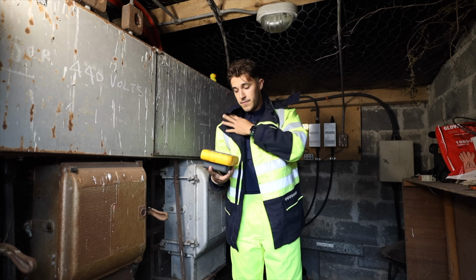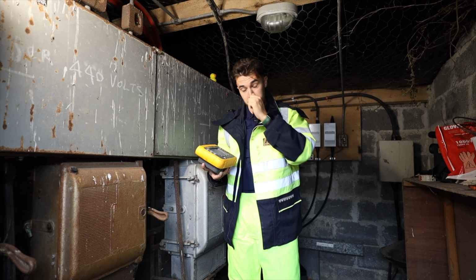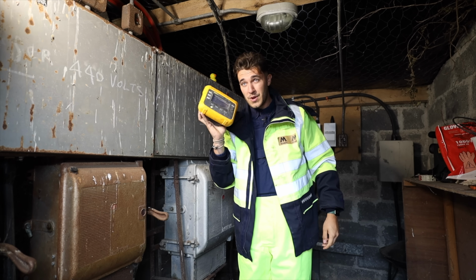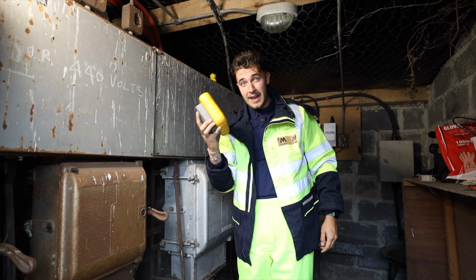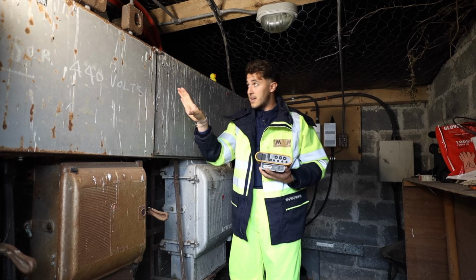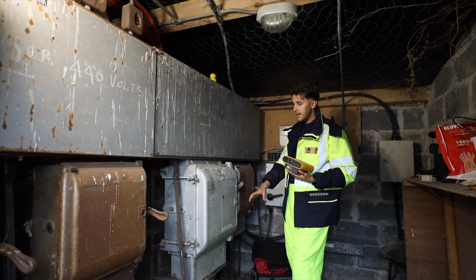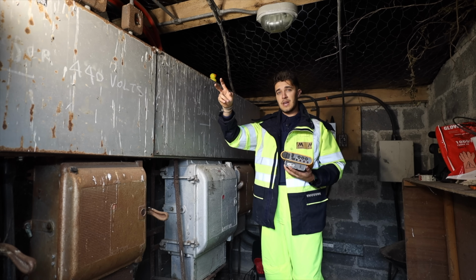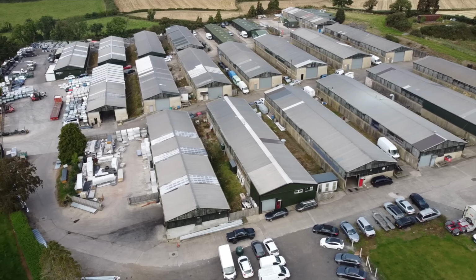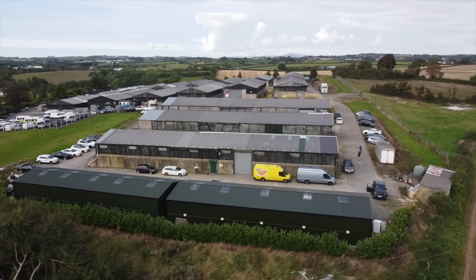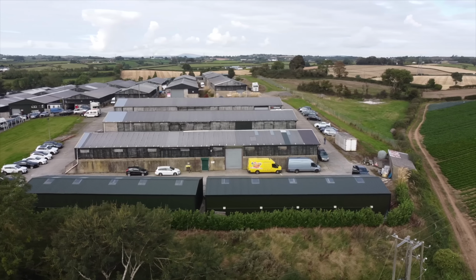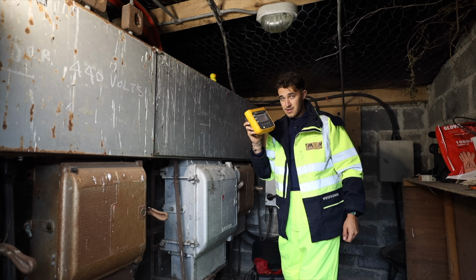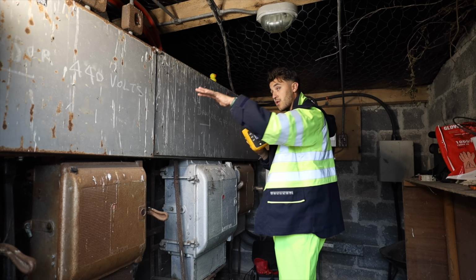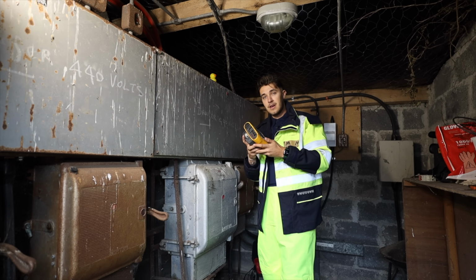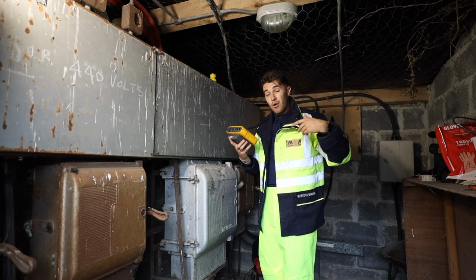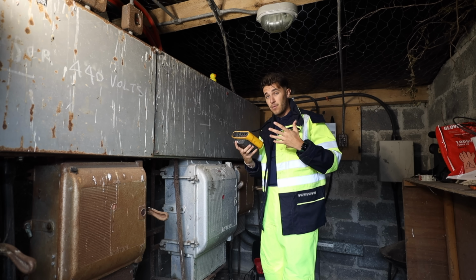Right, so now we can get the spider's webs off our face. We've got the data logger, so we can take this back to the office now and actually properly analyse the power. Just to reiterate, what this bus bar system's doing is powering this entire industrial estate. It was a load of chicken farms, but all these chicken sheds have been turned into different offices, garages, workshops, machine shops, etc. Now, inside this data logger, we've got enough data to see what the general consumption profile for this whole place is. So if we decide we want to put in a generator or solar or anything like that, we have a consumption profile, so we know exactly what we need.